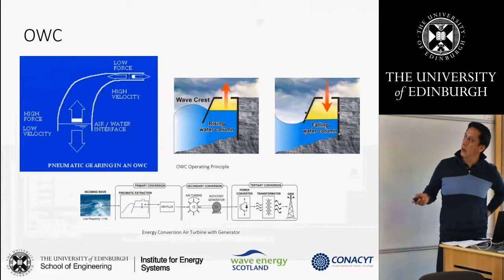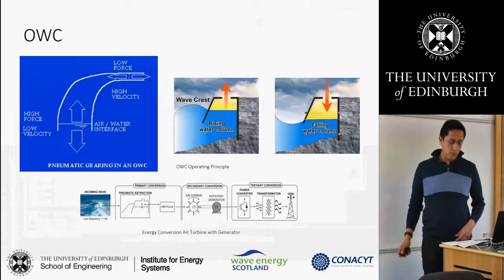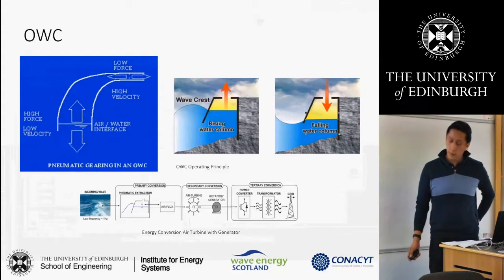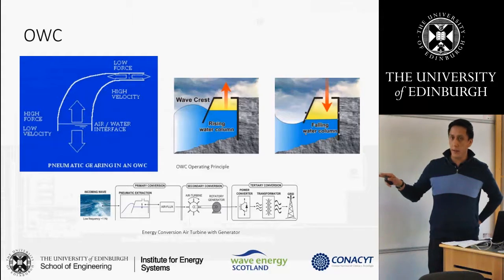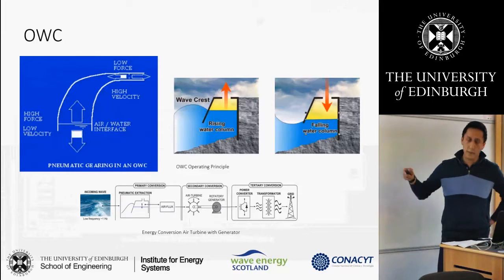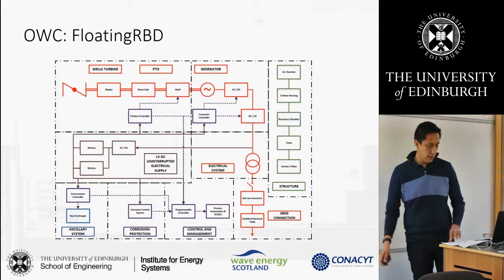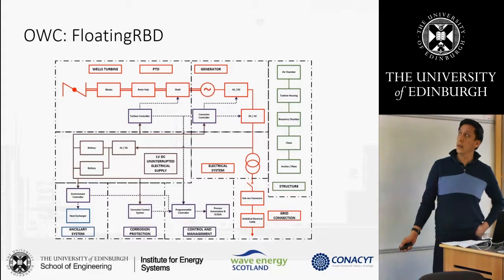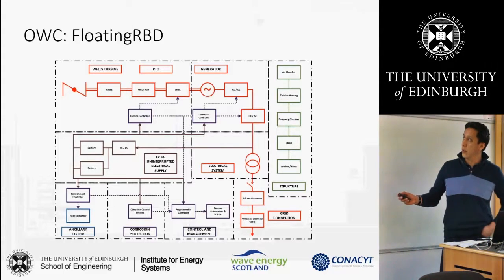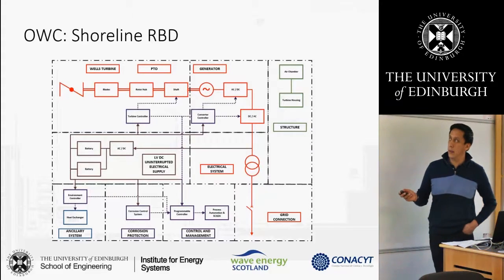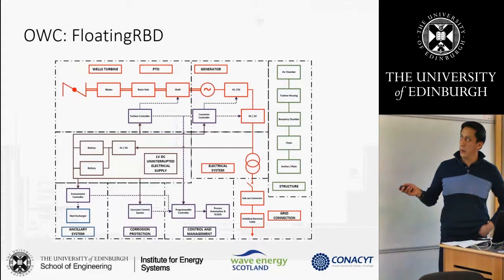For the oscillating water column, the power takeoff is just a Wells turbine, and the structure can be either shoreline-fixed or floating — that's where reliability changes, rather than in the power takeoff as with the point absorber. The reliability block diagram shows the floating oscillating water column has a more complex structure, while the shoreline version, fixed in a harbor for example, has a less complex structure — so the point of focus here is on the structure.